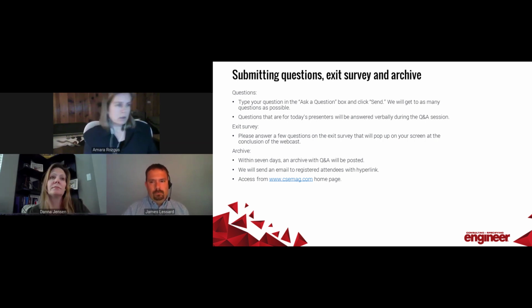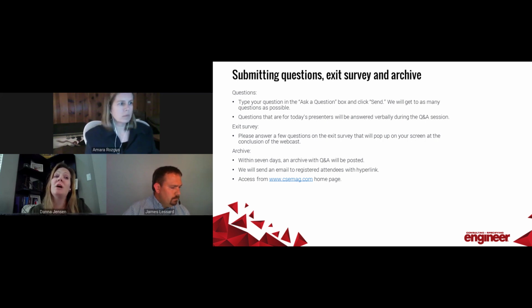Dana, next one's for you. You discussed the effects of high ambient temperature on that generator. Are there concerns in low ambient temperature environments as well? Yeah, there definitely are. The high temperatures get all the attention, but extreme low temperatures are a concern as well. So again, you have similar situations with inadequate oxygen levels, which could cause problems in startup. But another problem that could exist is actually the gelling of diesel fuel.